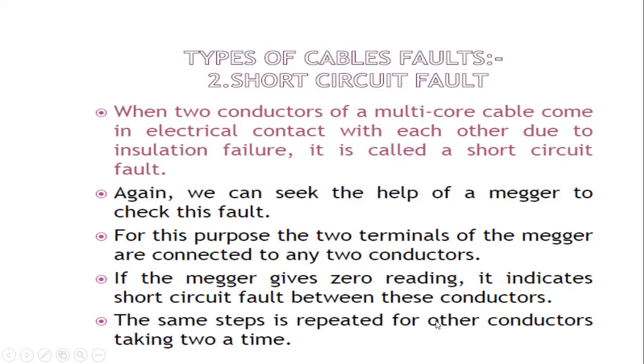The same step is repeated for the other conductors, taking two at a time. If the Megger does not measure a zero value, then there is no short circuit fault.